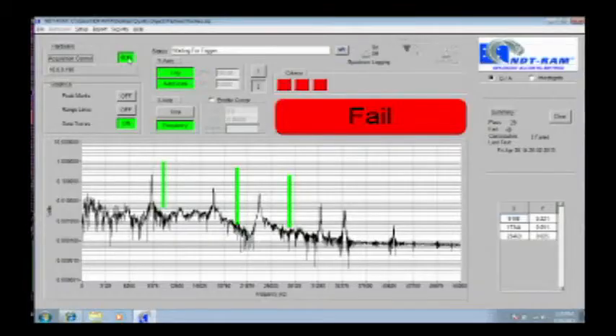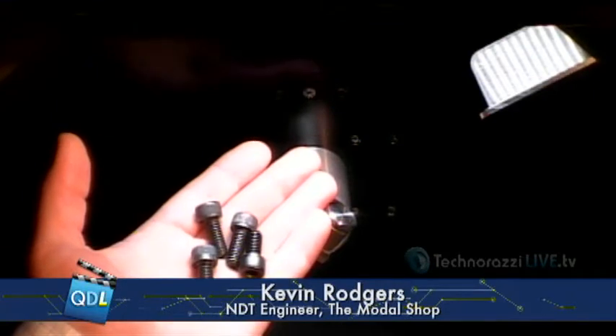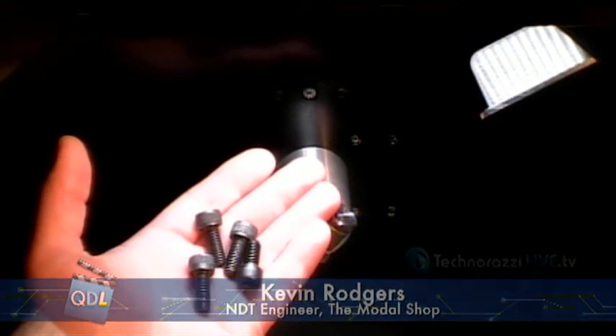Are people using your equipment for sorting or for pass/fail on parts? Typically it's for defect detection. We do have the ability to separate parts — sometimes materials or parts get mixed up and it's hard to identify one from the other. I have an example here: several 8mm screws, some are 20mm long, some are 16mm long. If they became mixed, we could run them through the machine, look at the signature of the part, and teach it which direction — pass or fail — each type should go.